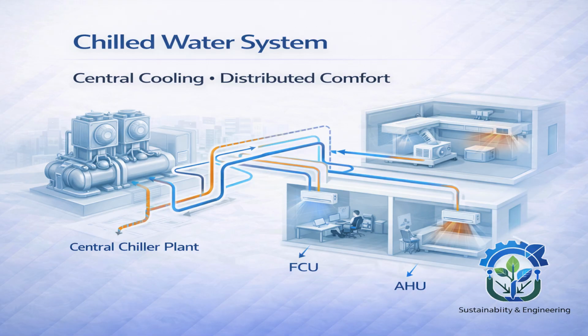Now let's understand why engineers use chill water systems. Chill water systems are selected when building size becomes large, cooling load is high, operation is long or continuous, and reliability is critical. Unlike DX or VRF systems, we are not depending on many small compressors scattered around the building. We rely on a few robust chillers designed for heavy-duty operations and maintained in one central location. This makes systems stable and predictable.